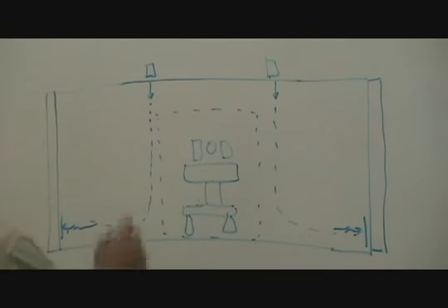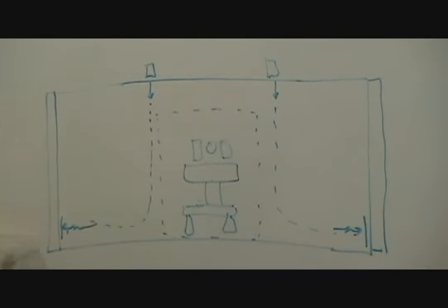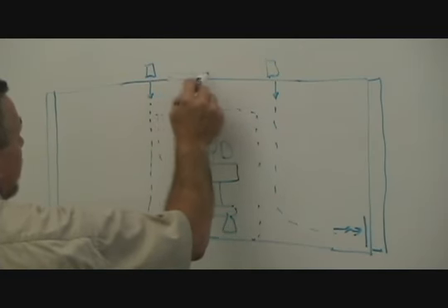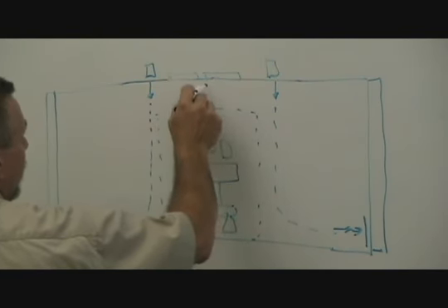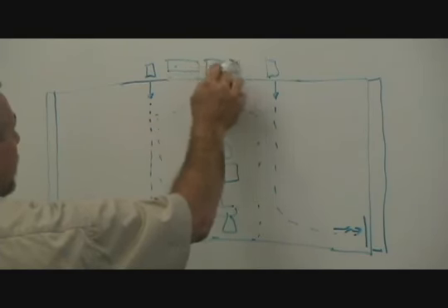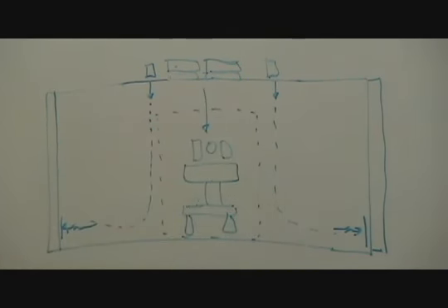So I create a perimeter around that stretcher to create a sterile zone in that stretcher. There are also laminar diffusers that can do the same thing. What I don't like about laminar diffusers, and these are dumping type laminar diffusers, is that unless I've got a HEPA filter right here that cleans that air, I'm dumping air right on that wound, open wound.